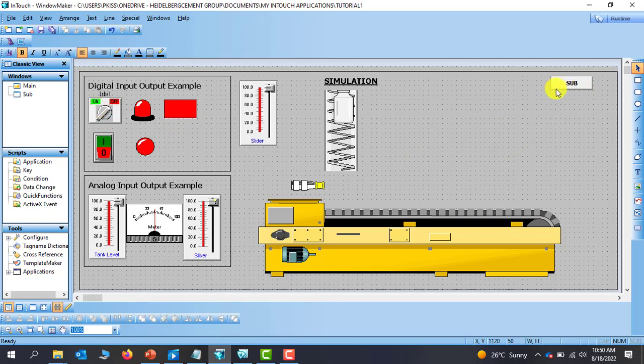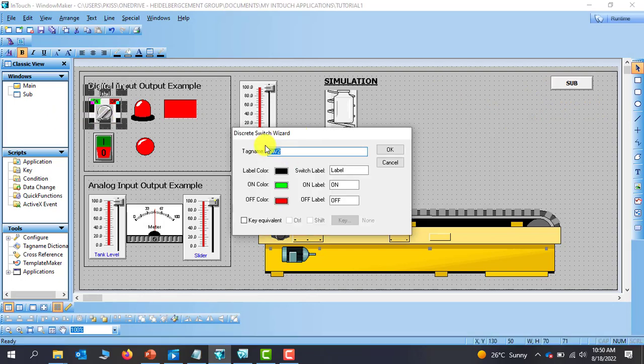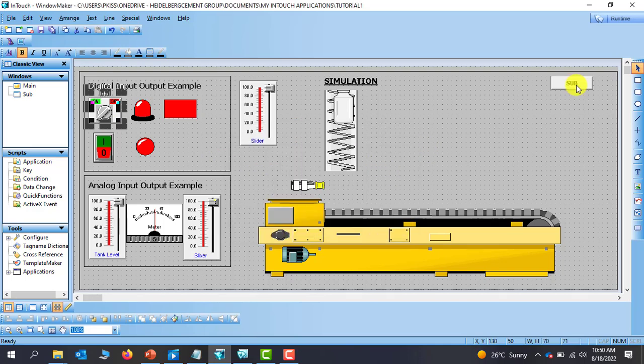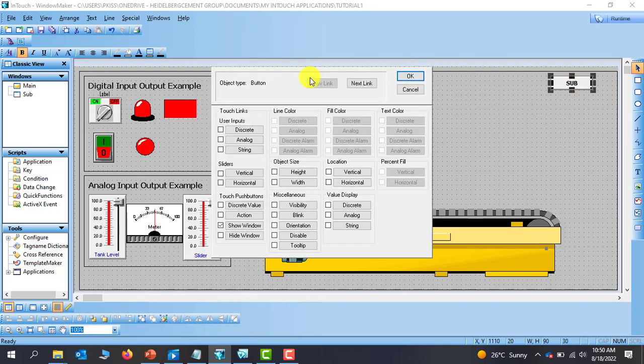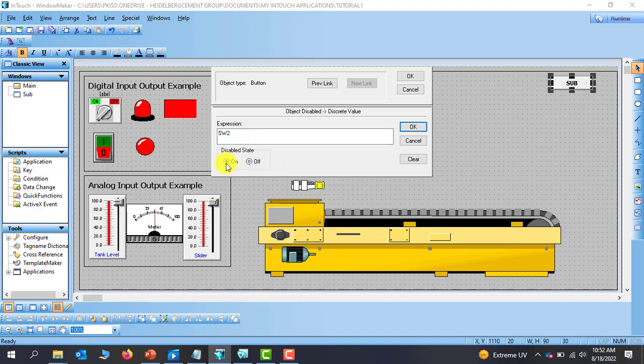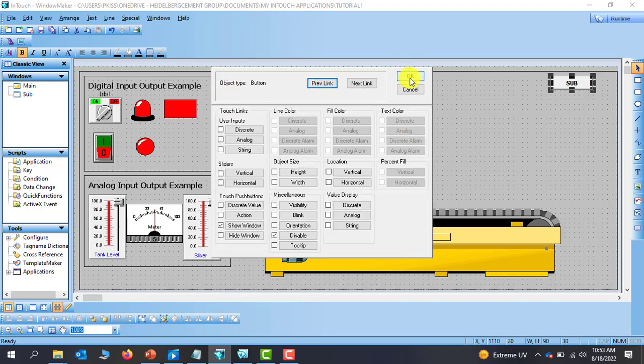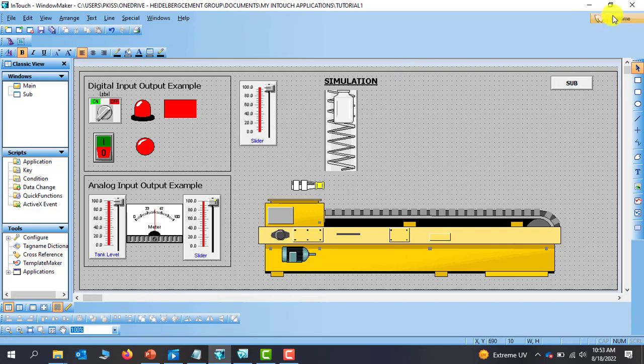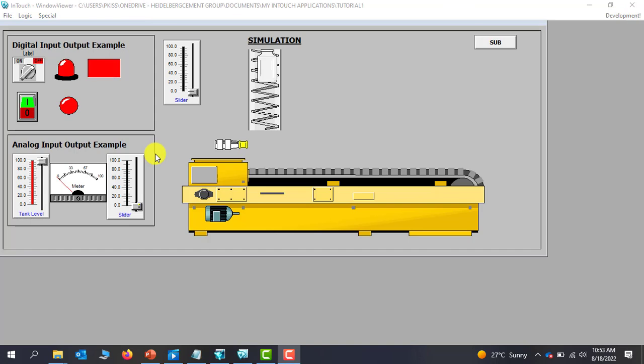First let's look at the switch tag. I copy it quickly and double-click to go to the property window. Under the same miscellaneous tab we can see the Disabled tab. I click on it and it's requesting the expression or condition for the disabling. Under the expression I put the tag that is going to do the disabling, and for the disable state I want the ON state — that's when I disable. I click OK and OK again.